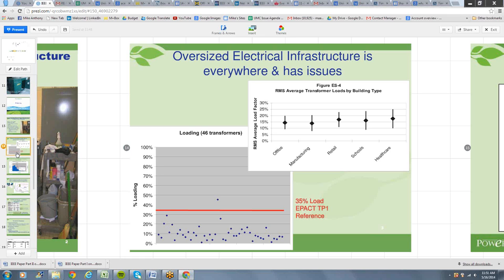As a result of that, the Cadmus Group, who in 1999 produced the study of these transformers, which you can see in the top right, found that 15 to 25% load is what's typical across all these vertical markets: offices, manufacturing, retail, and so on. Our own extensive field experience, which you can see in the bottom left, shows the loading of transformers. 35% is the EPAct 2005 reference load upon which efficiency requirements for transformers are based. You can see from that scatter plot that we're talking about much lower than that on average.